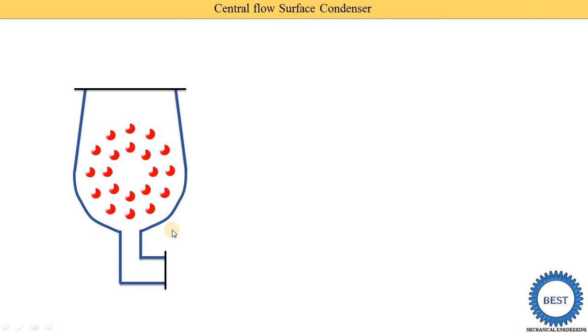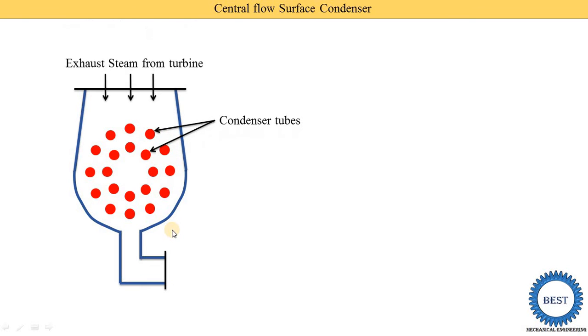Here you see the animation of the central flow surface condenser. These are the outer body or shell of the condenser. Inside this shell, there are a number of tubes through which water is passed. From outside the tubes, exhaust steam from the turbine is passed. This steam is condensed and collected in the bottom part of the condenser.